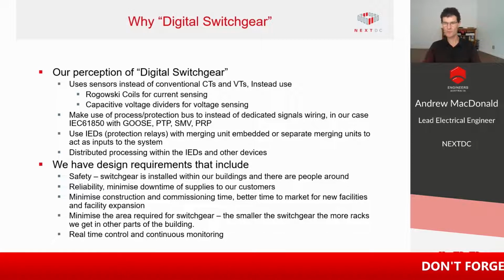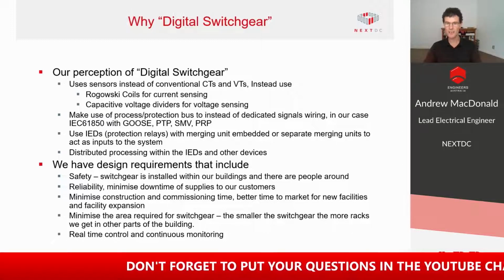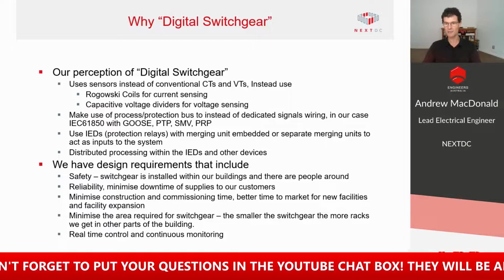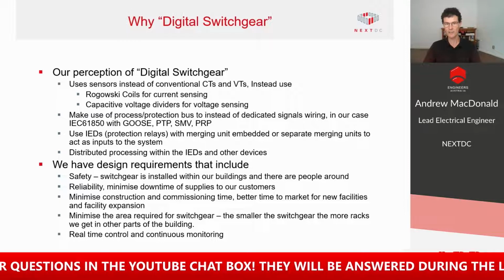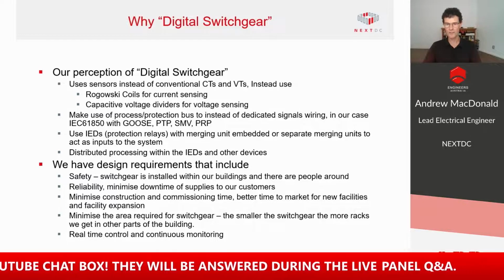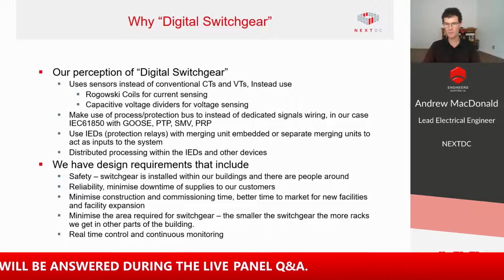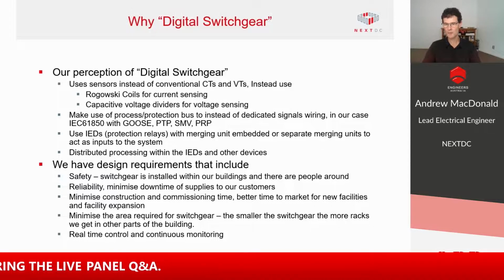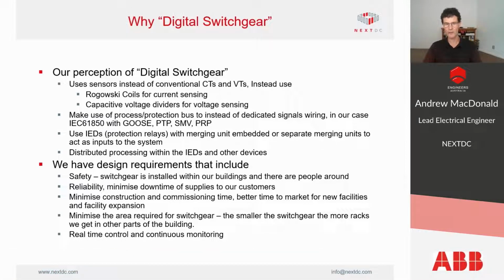Why digital switchgear? I'll start by introducing what we believe digital switchgear is. Our perception of digital switchgear is that we discard the use of conventional CTs and VTs, and instead we use Rogowski coils for current sensing and capacitive voltage dividers for voltage sensing. It makes extensive use of process and protection buses instead of dedicated signal wiring between the devices, and in our case we're using IEC 61850 with GOOSE, PTP, SMV and PRP, for those of you who understand what all the acronyms mean. We use IEDs, or protection relays, with merging units embedded or separate merging units to act as inputs to the system, with distributed processing across the IEDs and in other devices.